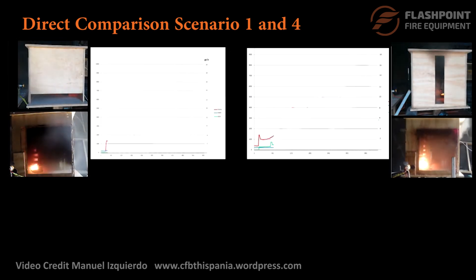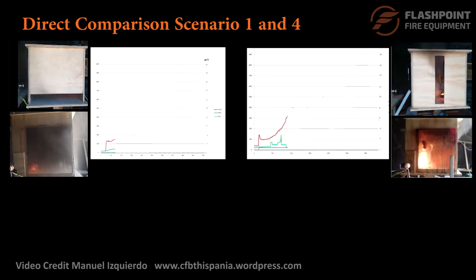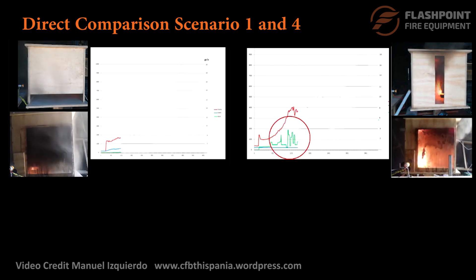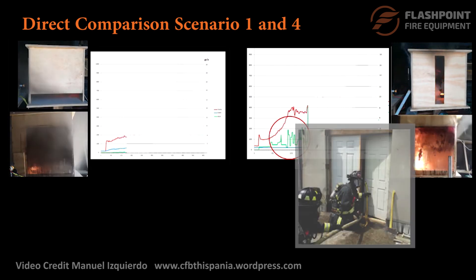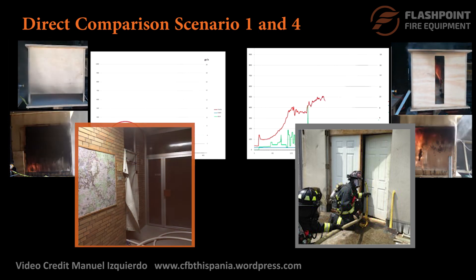Taking a direct comparison between scenarios 1 and 4 highlights the difference in orientation and position of a single narrow opening on the compartment. The highest heat release rate was achieved with a narrow vertical opening, similar to a manually controlled door. In direct comparison, the lowest heat release rate occurred with the single narrow opening positioned horizontally across the bottom of the compartment — the same configuration achieved by using a smoke stopper.